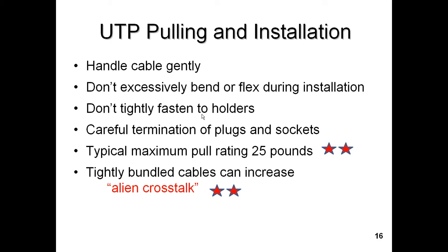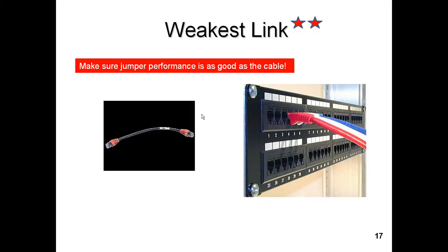When you go into a modern enterprise structured cabling system and you look at how they cable it, if it was done right or the way it's typically done, you'll see that they don't put the cables into tight bundles. They have cabling trays, or like a runner, and they lay the cable individually in the tray, and that's what carries it across the factory floor, or that's what carries a bunch of cables up the wall. They've got them spread out. They don't bundle them together. Bundling them together can cause problems. So remember that when you're doing your cable pulling.